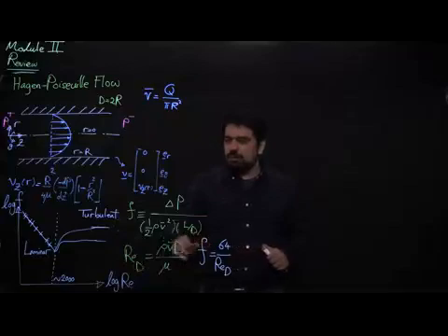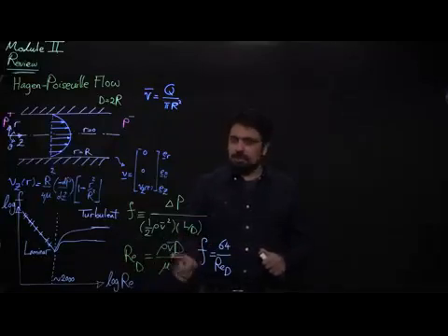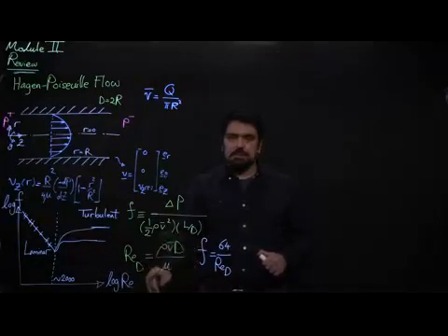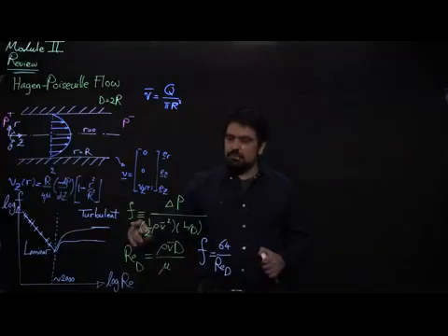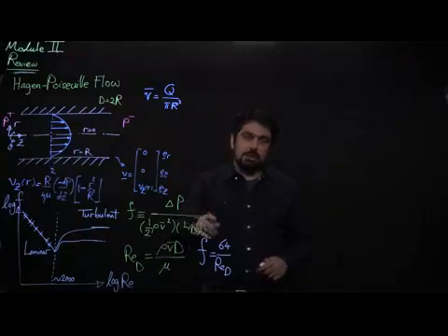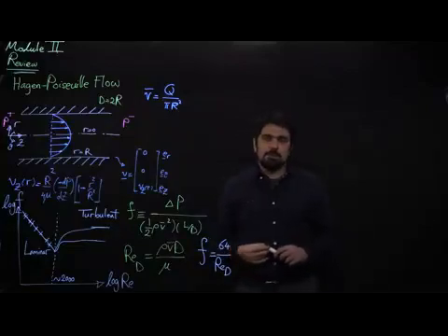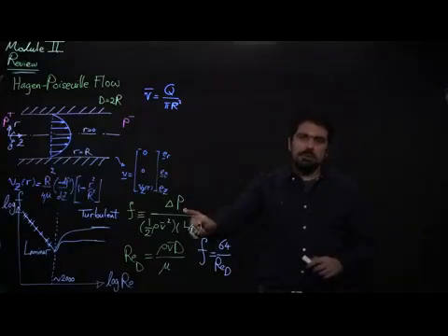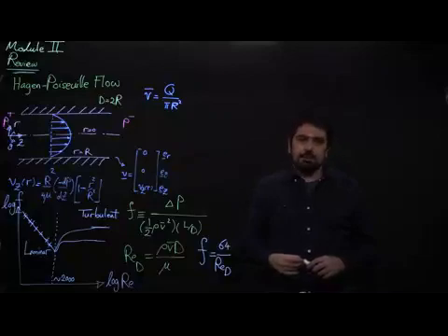For example, if you know what average mean velocity you need in a pipe, you use this relationship at a certain given Reynolds number for a given liquid like water with a certain viscosity and density, and you can actually calculate what the friction factor would be for the problem of interest, and that friction factor would give you back the pressure drop needed. So then when you go and design a pipe system and want to buy a new pump, you make sure that the new pump can actually guarantee this match of pressure drop for the desirable average velocity or average flow rate that you are planning to have in your pipe network.